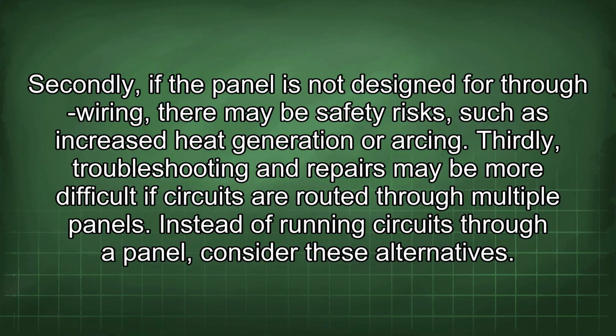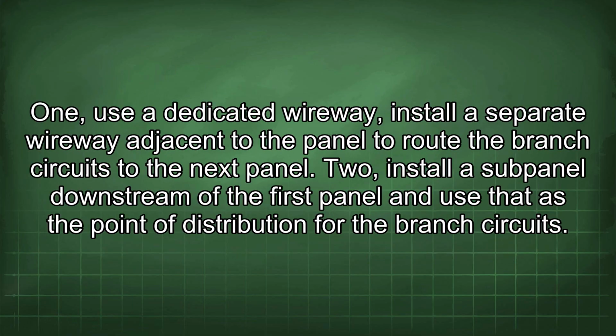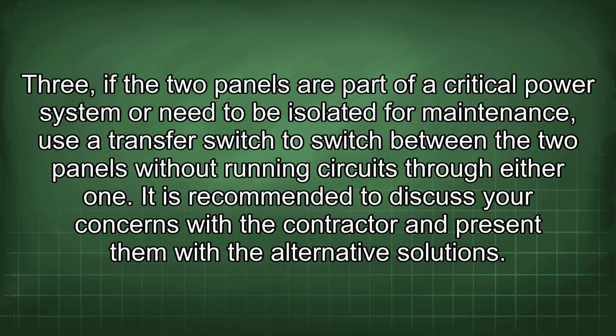Instead of running circuits through a panel, consider these alternatives. 1. Use a dedicated wireway. Install a separate wireway adjacent to the panel to route the branch circuits to the next panel. 2. Install a subpanel downstream of the first panel and use that as the point of distribution for the branch circuits. 3. If the two panels are part of a critical power system or need to be isolated for maintenance, use a transfer switch to switch between the two panels without running circuits through either one.